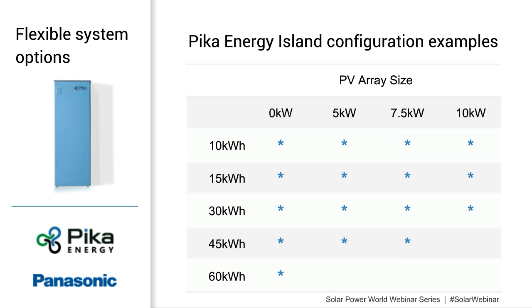So really pretty revolutionary that in the example of 10 kilowatts of PV and 30 kilowatt hours of storage, you have one inverter, two batteries, and you'd have 4 of our PV Link optimizers, and that's it. So really a low part count for a huge amount of energy capacity and power capacity as well.